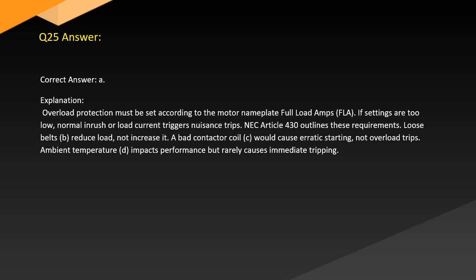Answer. Correct answer: A. Explanation. Overload protection must be set according to the motor nameplate full load amps. If settings are too low, normal inrush or load current triggers nuisance trips. NEC Article 430 outlines these requirements. Loose belt, B, would reduce load, not increase it. A bad contactor coil, C, would cause erratic starting, not overload trips. Ambient temperature, D, impacts performance but rarely causes immediate tripping.